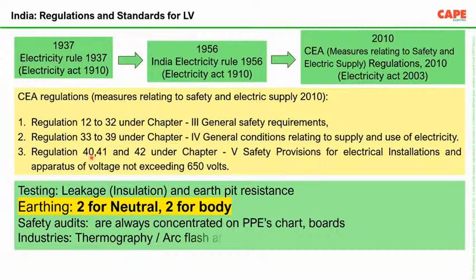Then, safety audits. Wherever we do an industrial or commercial safety audit, the more concentrated subject is sometimes the insulation resistance test, and most commonly the earth pit resistance test. And safety audits are always concentrated on what kind of PPEs are used, what kind of charts are there, what kind of boards are there. There are even safety audit reports where I have seen it noted that the size of the danger board is smaller. As a result, you lose complete safety. These are actually not the important factors. The basic tests which I have shown are the most important. PPEs, charts, boards and other things are one line. Everybody should follow it, that's it.